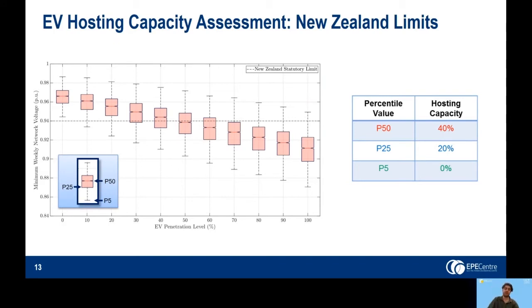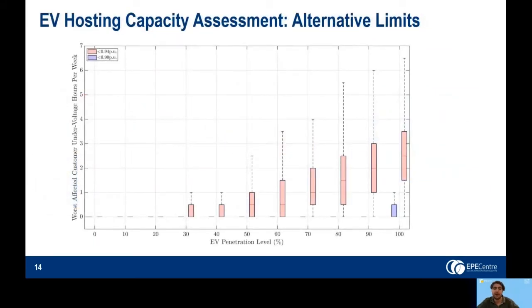That is, that all voltages must be within plus or minus 6% during all of the time. Even at the 0% penetration level, there is a chance, albeit a very small one, that a voltage violation will occur. In reality, customer loads should be able to tolerate a small number of minor undervoltages. Shown here is a plot of the number of undervoltage hours per week for the worst affected customer in the network. Again, the x-axis shows the EV penetration level.